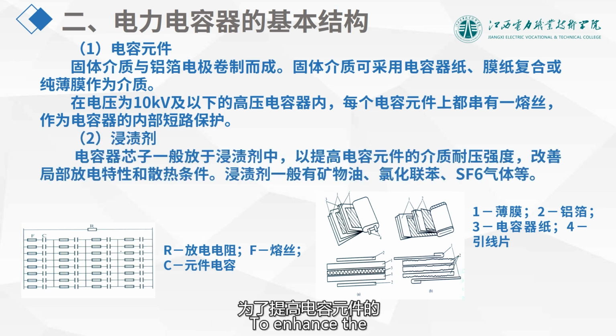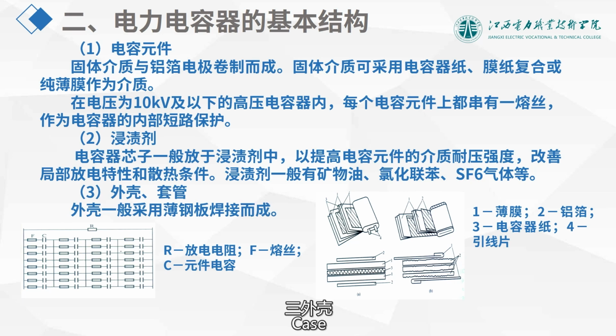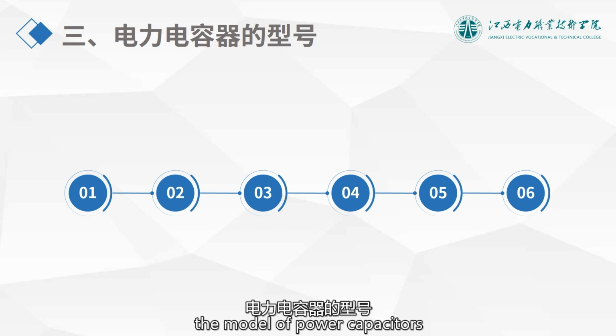Impregnating agents enhance the dielectric strength of capacitor elements, and improve partial discharge characteristics and heat dissipation conditions. The capacitor core is generally immersed in mineral oil, chlorinated biphenyl, SF6 gas, etc. Case bushing. The case of the capacitor is generally welded from thin steel plates for better heat dissipation, but the insulation performance is poor. Next, we will introduce the model of power capacitors.